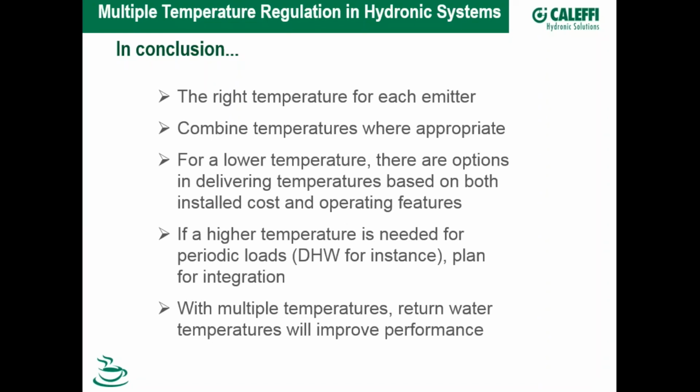So I like it both ways. I like the idea of having control with the TT contact, but in reality, my goal always is to drive the water temperature down as low as possible, which pushes me to outdoor reset and continuous circulation, which means there's going to be a constant call on the system as it stands.